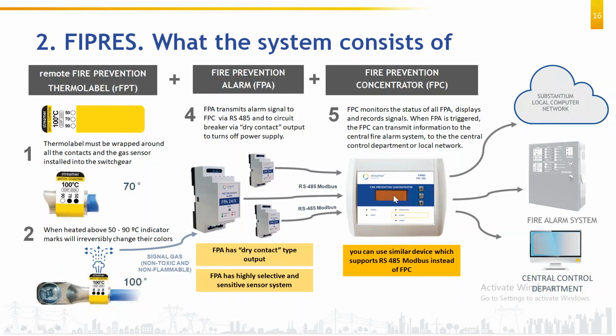All right, and then the FPC will display the status of all the alarm points, and it has the capability to communicate to a remote PC through the Ethernet port, Modbus TCP/IP. It can communicate to a local substation, or it can communicate to a fire alarm system or a local control department. So this is the complete configuration. In a particular system, we are going to install such stickers on all the joints, on all the cable terminations. In every cabinet, we are going to install an FPA, and we will have one FPC to monitor the status of all the FPAs. This is the system configuration.